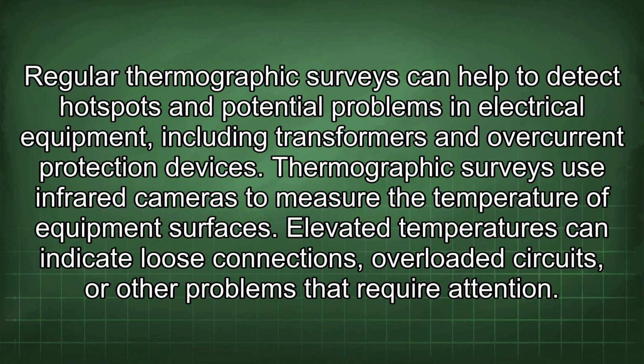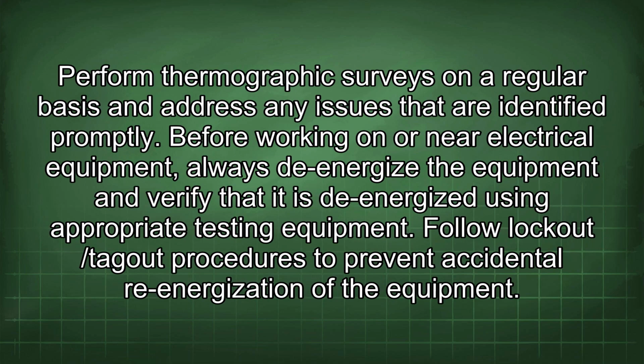system. Regular thermographic surveys can help to detect hotspots and potential problems in electrical equipment, including transformers and overcurrent protection devices. Thermographic surveys use infrared cameras to measure the temperature of equipment surfaces. Elevated temperatures can indicate loose connections, overloaded circuits, or other problems that require attention. Perform thermographic surveys on a regular basis and address any issues that are identified promptly.